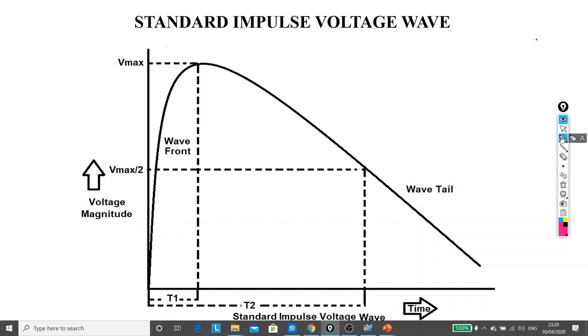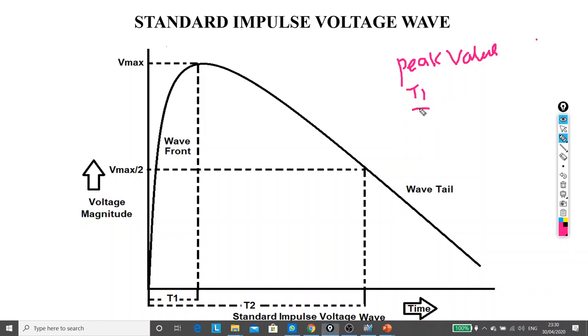This figure shows the standard impulse voltage waveform. If you observe this waveform, it is specified by three parameters: mainly the peak value, then the rise time T1, and the time to decay to half of the peak value on the wave tail — from the zero value to the peak, and from the peak to half of the peak value on the wave tail. That duration is T2. So a standard impulse voltage wave is always specified by these three parameters: peak value, rise time, and time to decay to half of the peak value. For example, 1.2 by 50 microsecond.